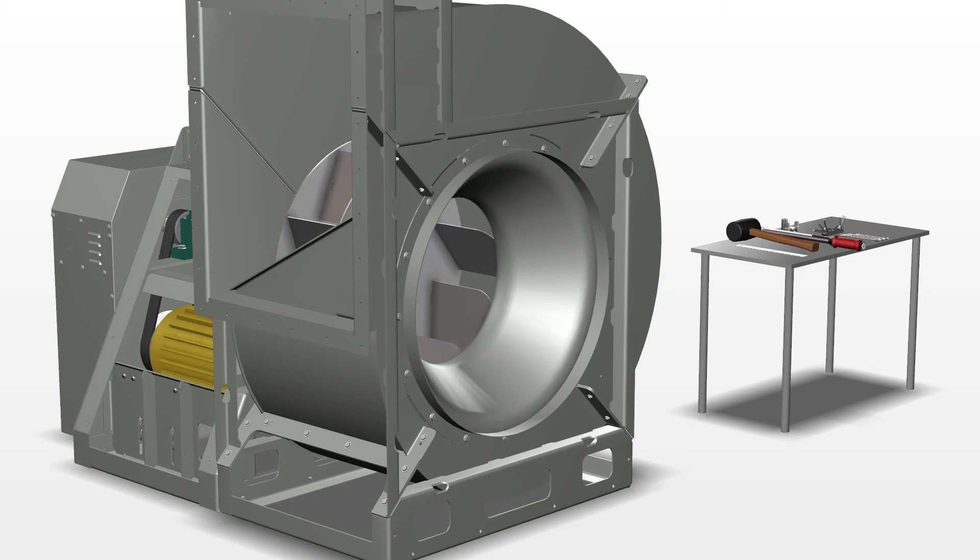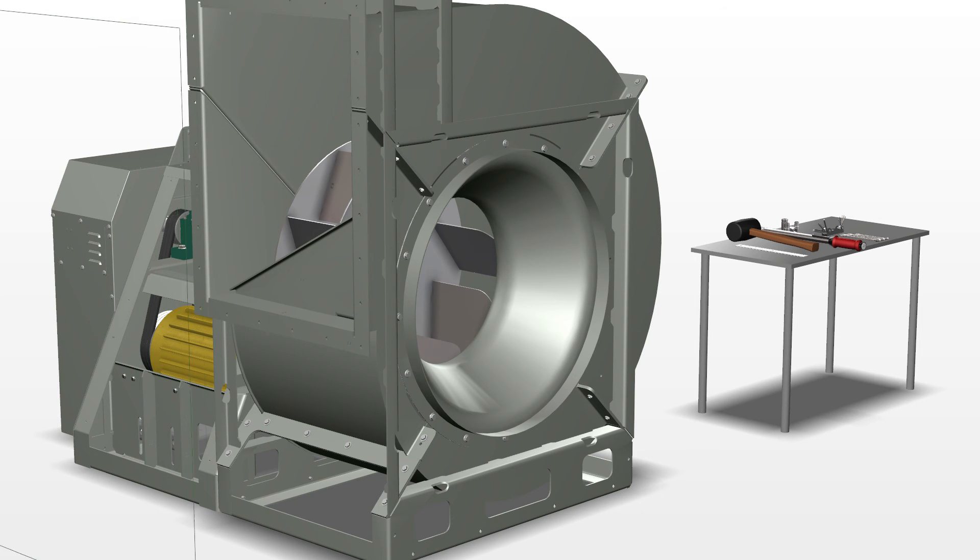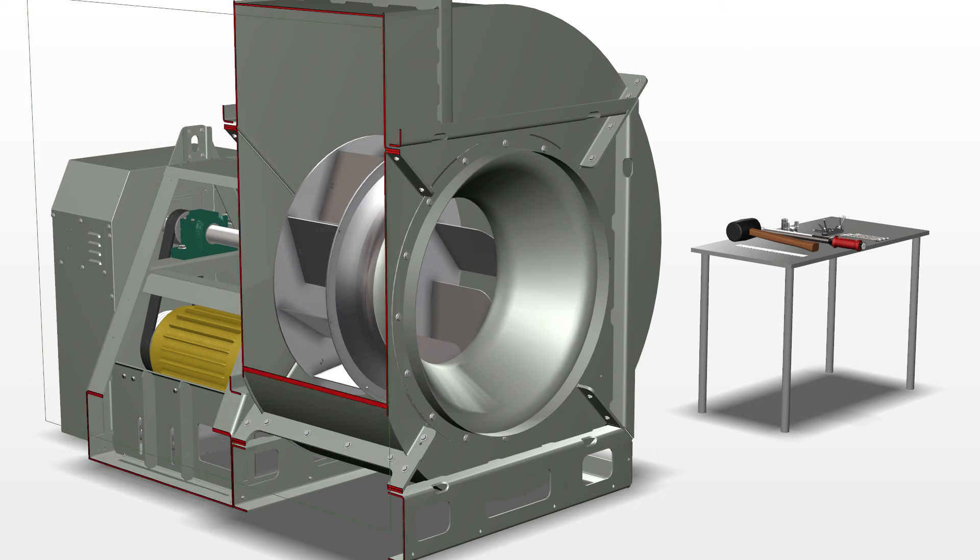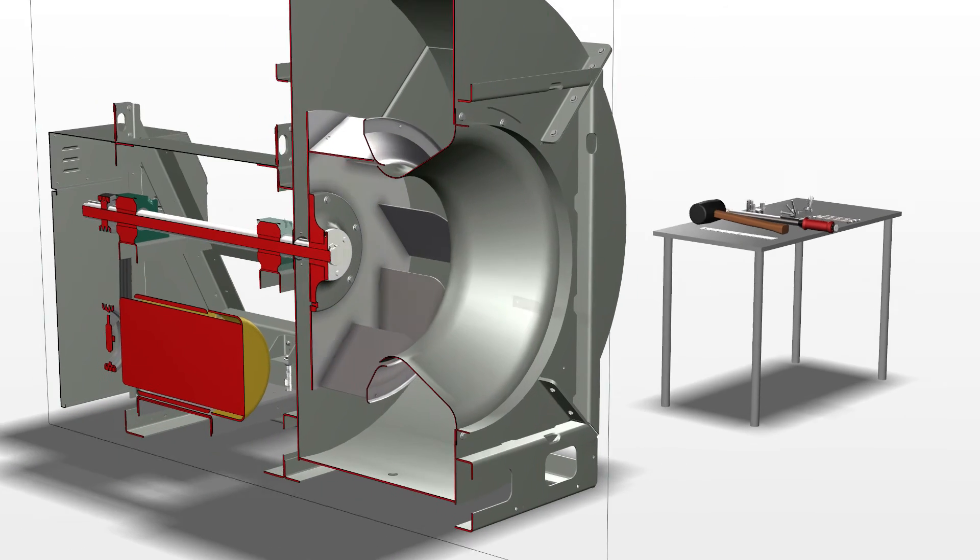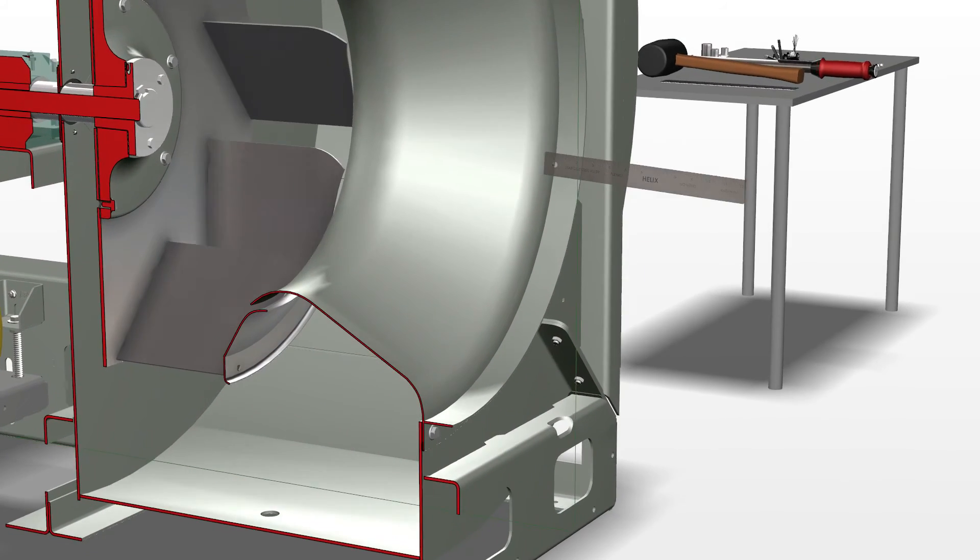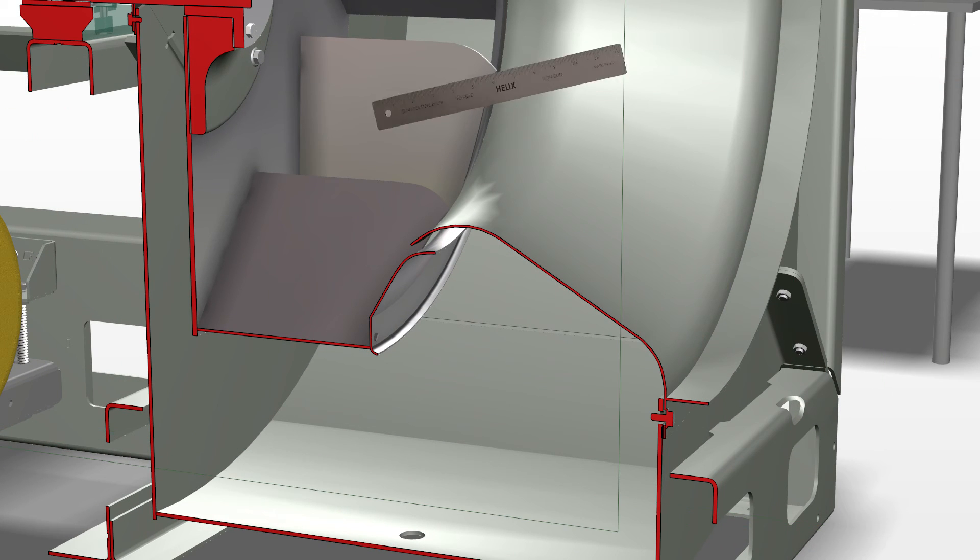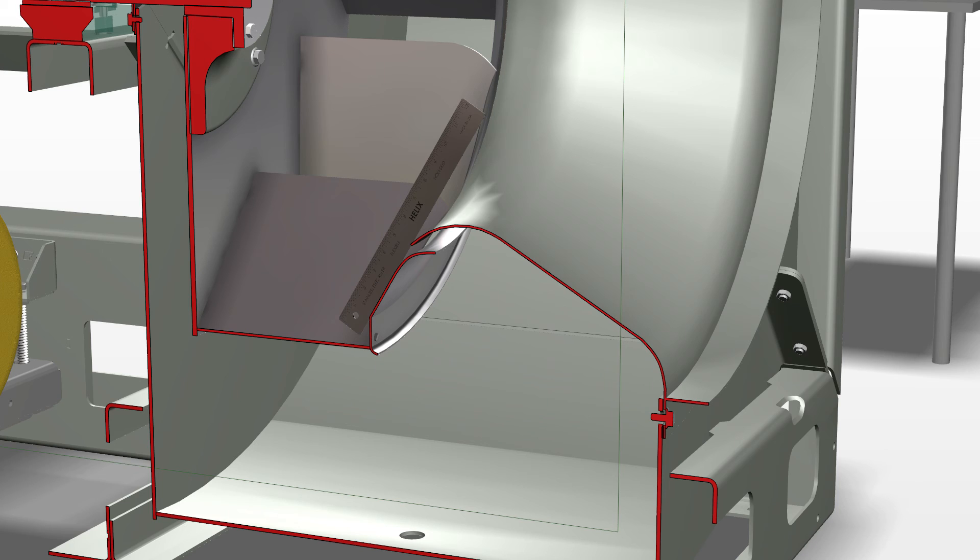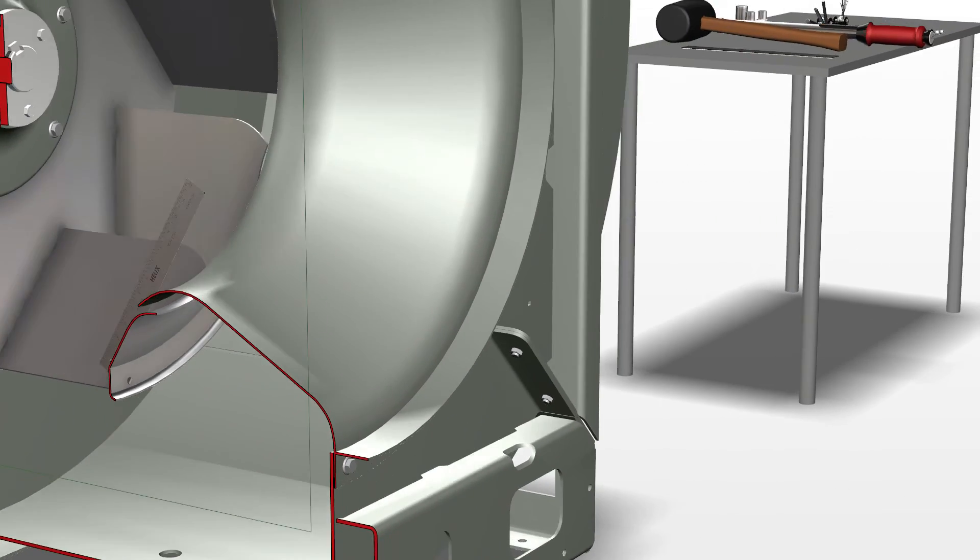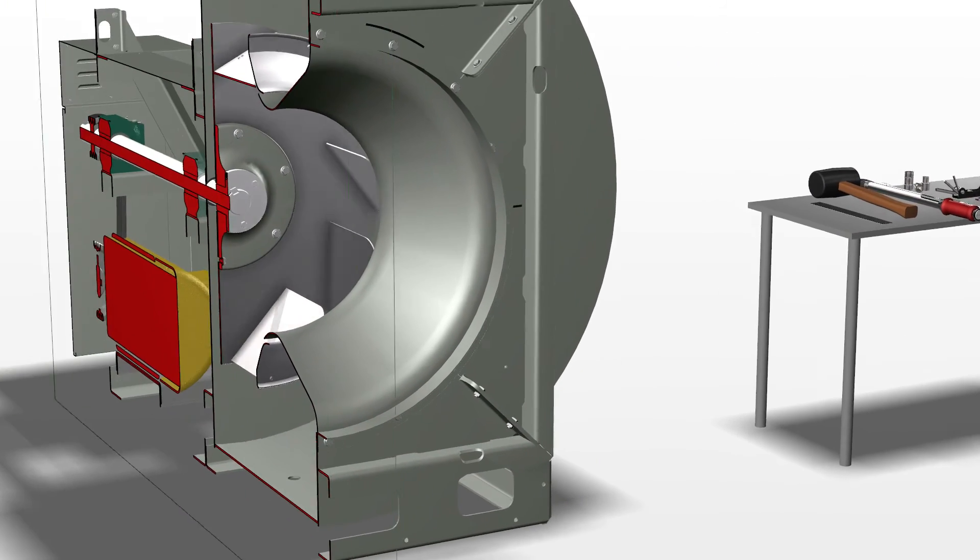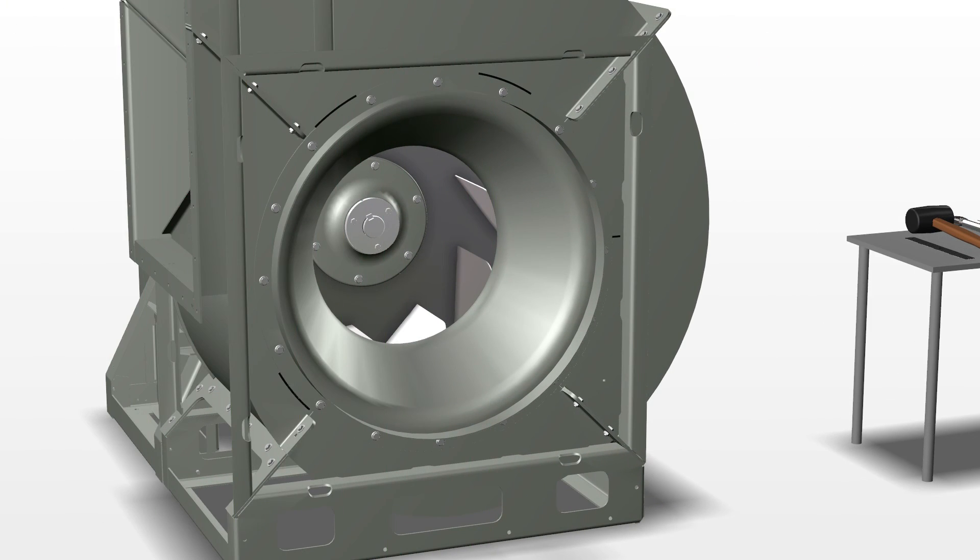If necessary, you may need to adjust the wheel positioning by loosening the wheel hub bolts and set screw. Take a straight edge and hold it tight against the wheel cone just so it touches the inlet cone as shown in the diagram. Once the inlet cone and wheel overlap are correct, use the torque wrench to tighten the set screws and wheel bushing bolts according to the manufacturer's recommendation.